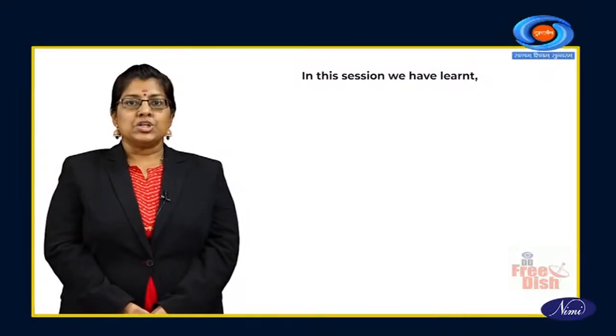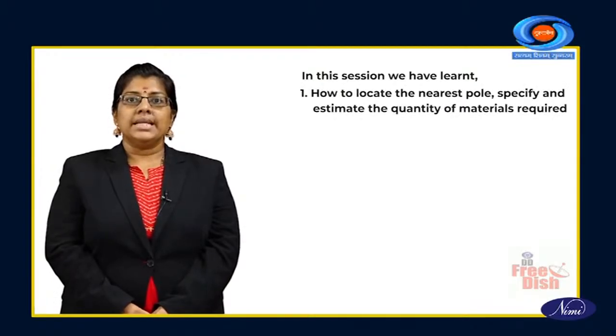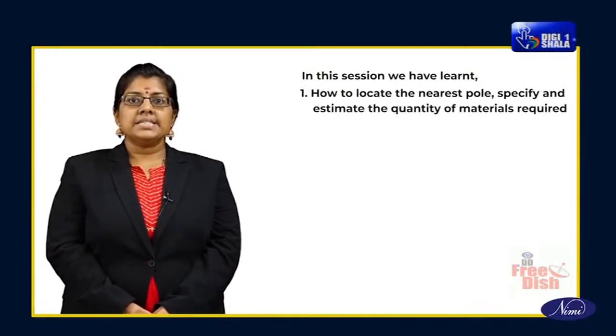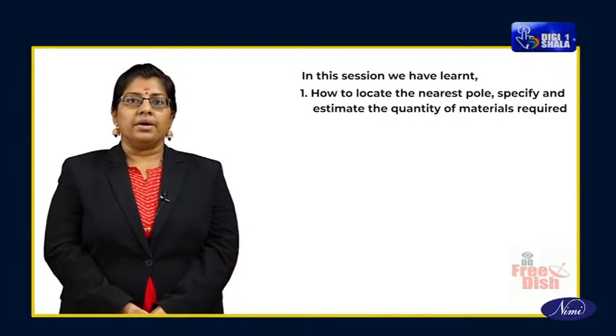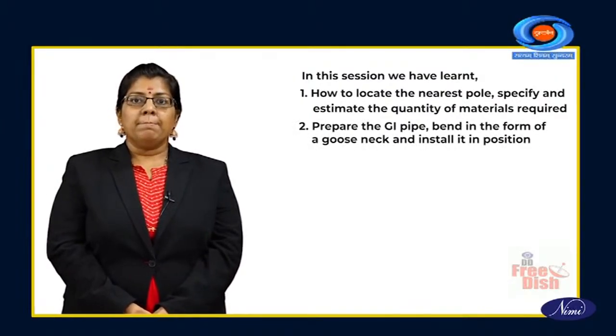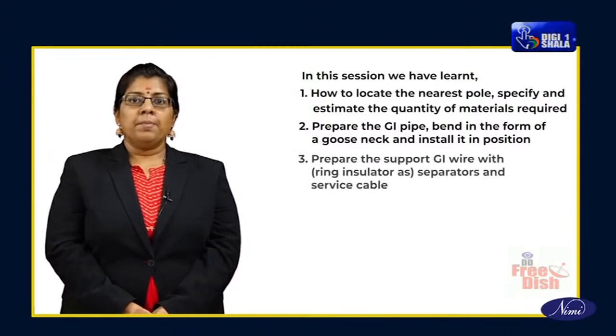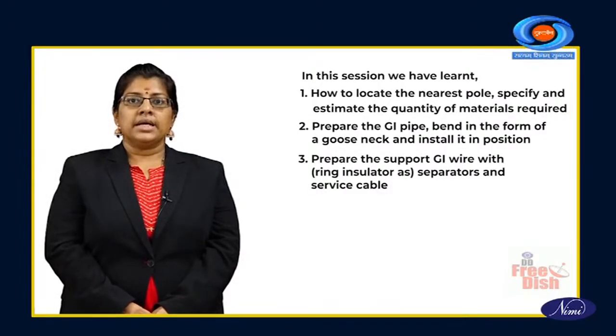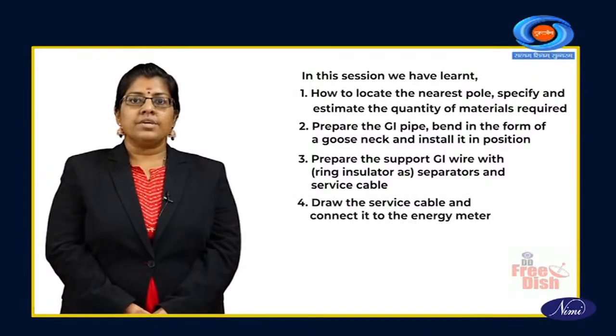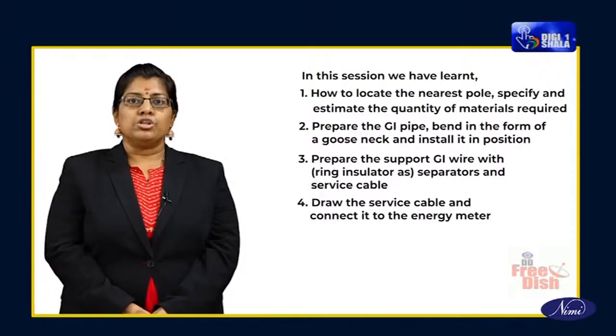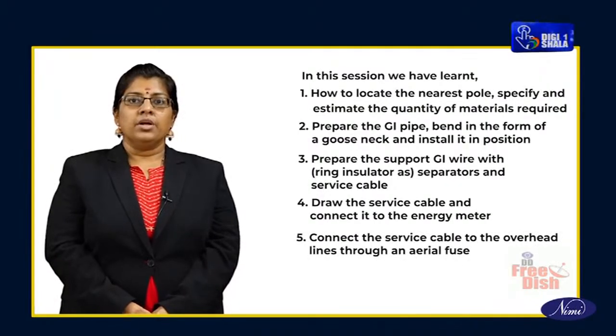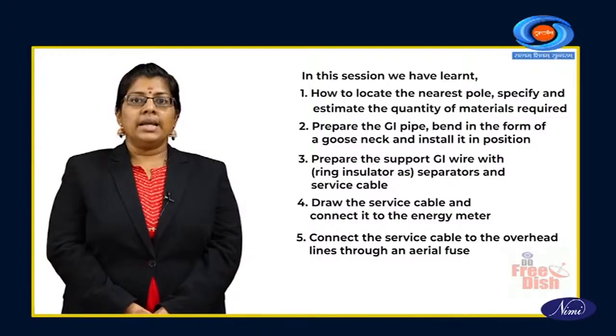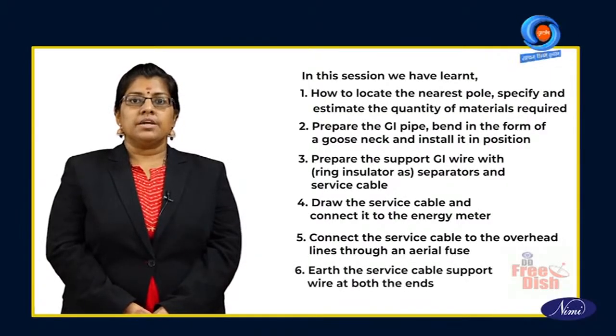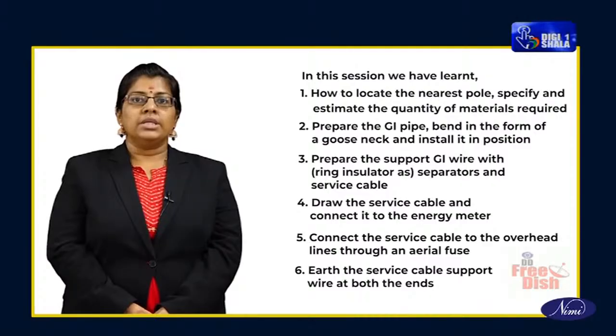Recap. In this session, we have learned how to locate the nearest pole, specify and estimate the quantity of materials required. Prepare the GI pipe, bend in the form of a gooseneck and install it in position. Prepare the support GI wire with ring insulator as separators and service cable. Draw the service cable and connect it to the energy meter. Connect the service cable to the overhead lines through an aerial fuse. Earth the service cable support wire at both the ends.